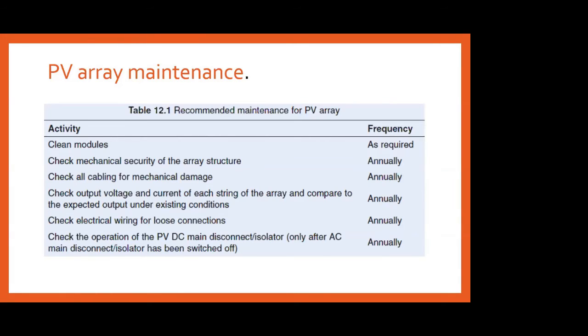Okay, starting with cleaning the modules, it depends upon the frequency, because it will not be the same throughout the year, and it will not be the same for different geographical conditions. Then check the mechanical security of the array structures, and check the cabling for any mechanical damage. Check the output voltage and current of each string of the array and compare with the expected output under the existing conditions. Check the electrical wiring for loose connections, and check the operation of your PV DC main disconnector or isolator, only after the AC main disconnector has been switched off. Okay, these are some of the recommendations given by the manufacturer for maintenance of your PV array.